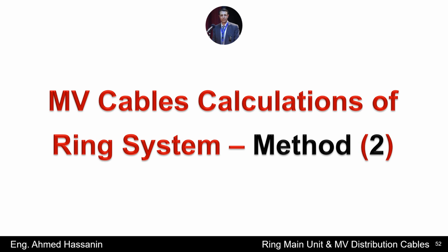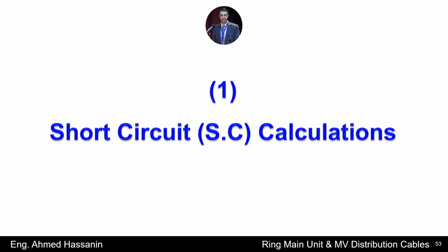In addition, and in detail, I will explain the second method for calculating the medium voltage cables of the ring system. Don't forget that in the first method, I will start by calculating the load current and thermal current for the medium voltage cables of the ring system. However, in the second method, I will start by calculating the short circuit current that the medium voltage cable can withstand at any fault. In addition, I will explain the difference between the first steps in each method.